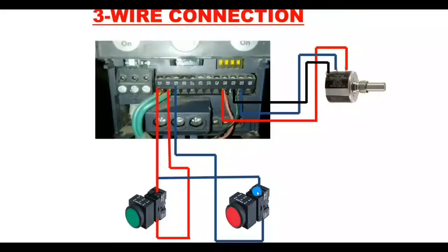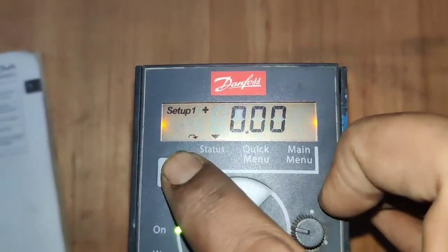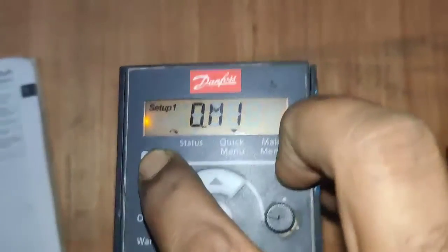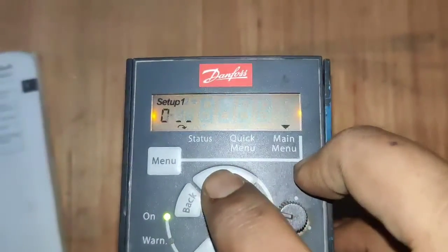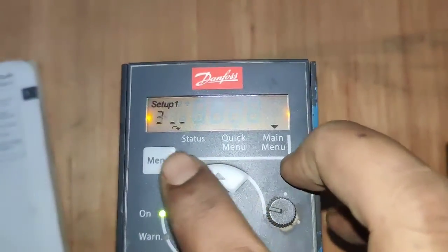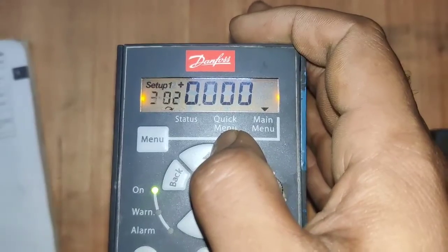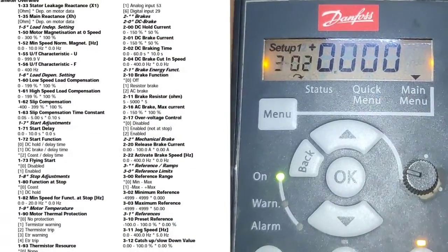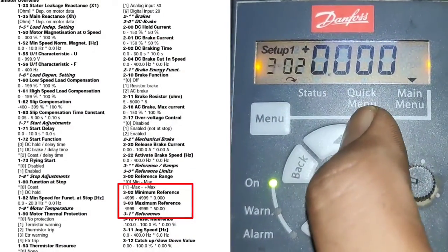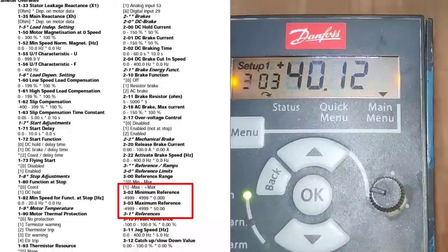Now let's learn how to do the proper parameter setting for this control wiring. First press the menu button — it will show QM1. Press menu again and enter the third parameter group. In the third group, parameter 02 is for minimum frequency, and parameter 03 is for maximum frequency at which the motor will run.